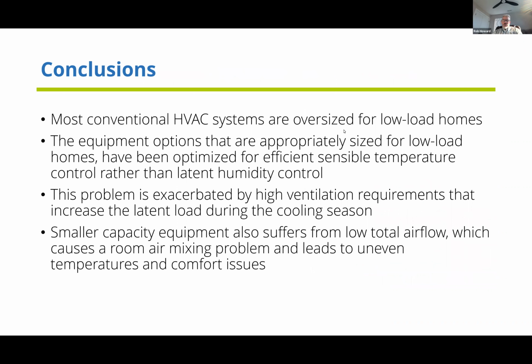Just some conclusions - not the conclusion of my presentation, just my graduate research - were that most conventional HVAC systems are oversized for low load homes. The equipment options appropriately sized for low load homes have been optimized for efficient sensible temperature control, but not necessarily for latent control. This problem is exacerbated by high ventilation requirements that increase the latent load during the cooling season. It's really a perfect storm, and one of the few options to solve it is supplemental dehumidification.